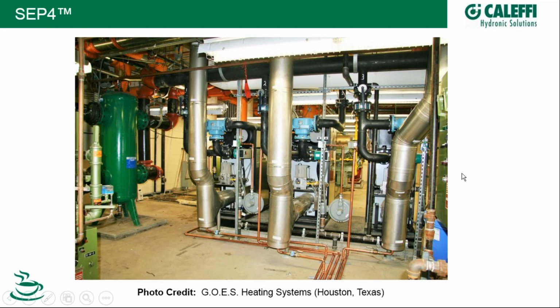Now, off to the right here, a lot of these systems down there in Texas are condensing boilers. Now think of where you're at. You're down in Texas. You don't have a long heating season. Condensing boilers are typically, for these size units, more pricey, but they're significantly more efficient. So most of the season down in the Houston area, you don't have a peak load. They're more expensive, but they're more efficient to operate, more cost effective.